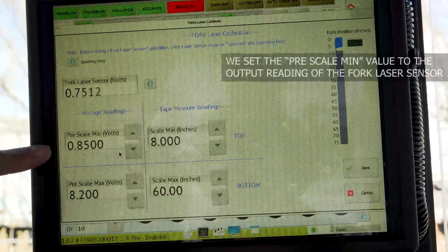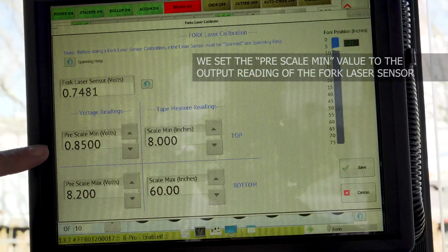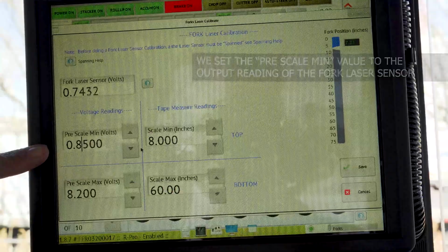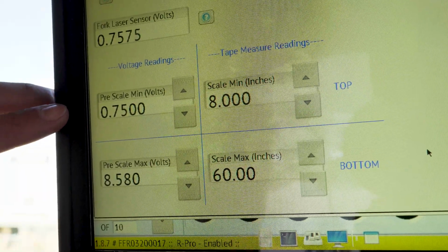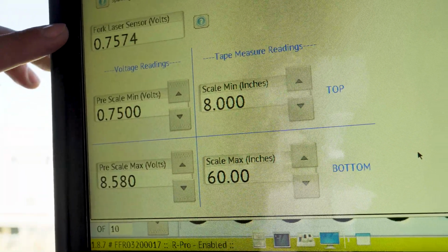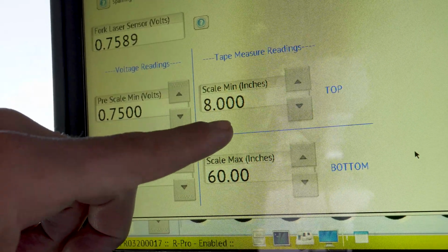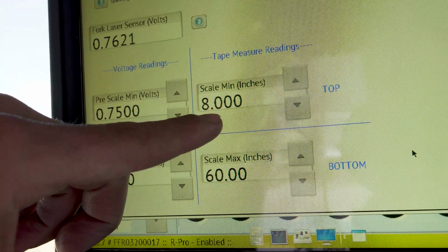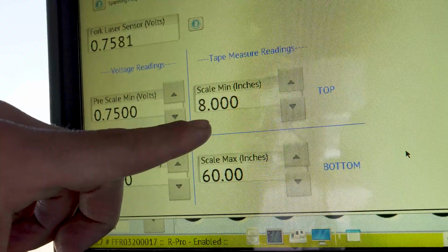So we're gonna change our pre-scale min voltage to 0.75. Now that we've set our pre-scale min volts to what the reading is, we need to make sure that our scale min inches is set to what the tape measurement reading is, which is 8 inches.